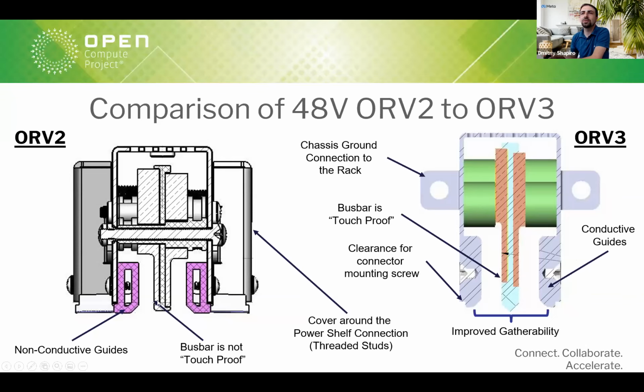The bus bar on ORV2 was not touch proof, so there's a pretty open gap and the conductors are fairly close to the front, so you could get your fingers in there potentially. On ORV3, we moved the conductors back and made sure that at all angles of entry through a standard UL probe, you are not able to touch these conductors.